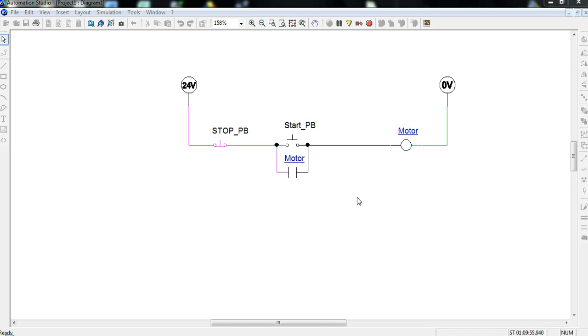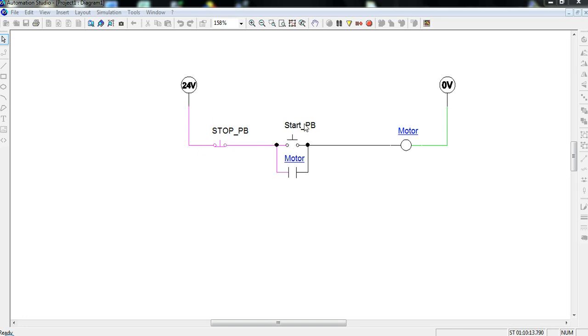We have a stop push button and it's wired normally closed. When we say normally closed we mean in its normal position it is closed. The stop push button in closed position allows current to flow through. The start push button is open so we have no continuity. This is in a normally open position. In our normal position our start button does not allow current to flow through. When I say normal I mean not pushed, not actuated.